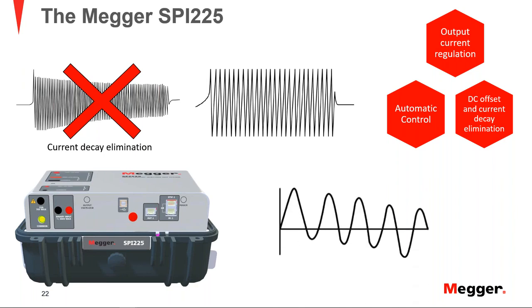Next is DC offset, which is something that we have to be very careful with. Traditional units will have to go into the settings and adjust, for example, the firing angles, so we can ensure that we don't see this type of behavior. A DC component will cause that, especially for those tests where we're measuring instantaneous trips, where the breaker will trip seeing a higher current in those first few cycles. So the algorithms and the electronics in the SPI will make sure that you don't have that issue, so I can guarantee constant current in the output.